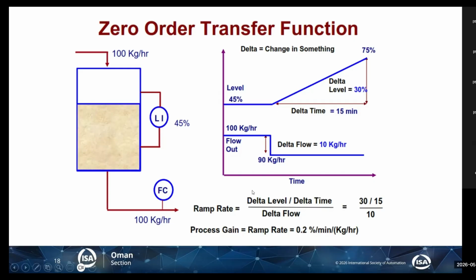And to calculate it, you will have to take the change in level, like it was 45, then 75, and the change in time, which is 15 minutes, and we divide it by the change in flow, which is 10. Then we get our process gain for the zero order, which is ramp rate. And it is very important to understand that in this system, if I open the valve 1%, I will get 0.2 change in the system.